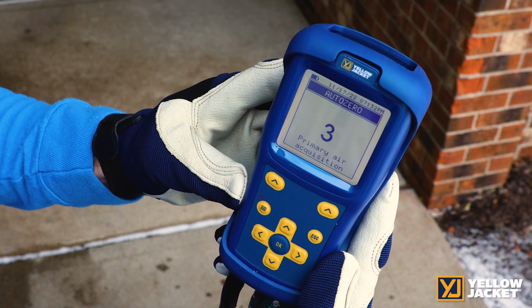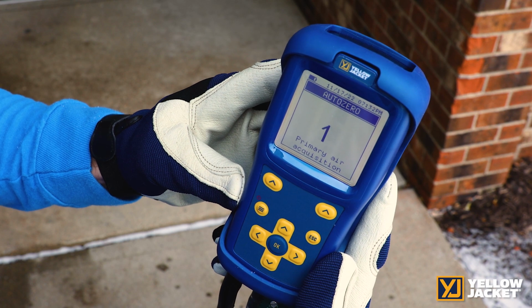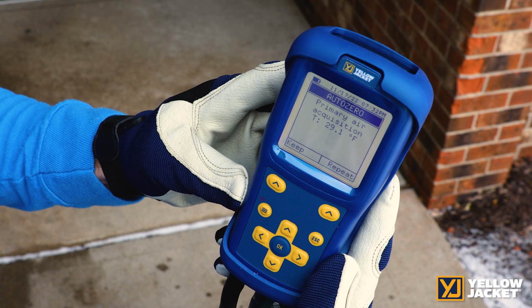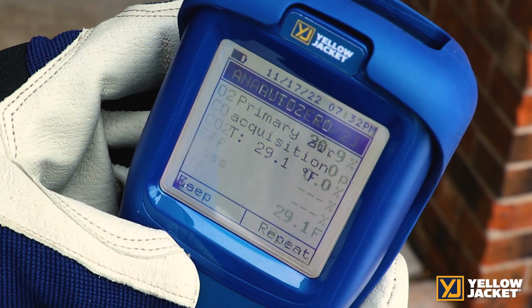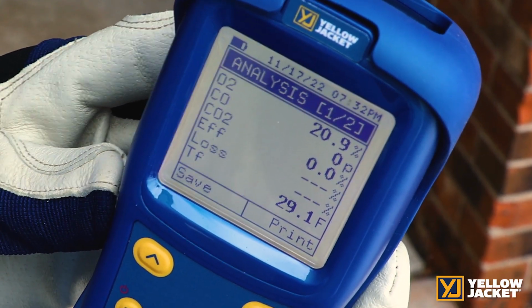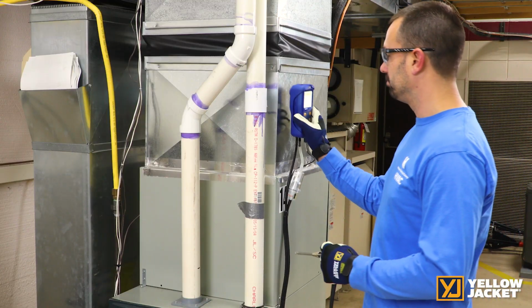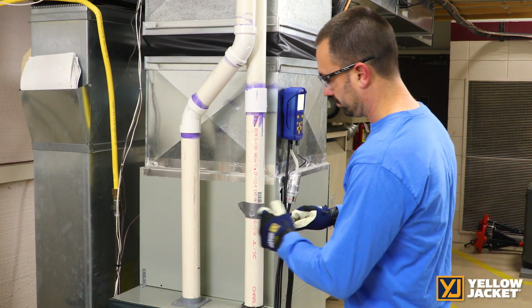This step starts the warm-up cycle and verifies the machine is operational and working properly. You will be asked to keep or repeat to reset your zero. If you started in an area where there may be a CO issue, go to the fresh area and hit repeat. Once you have a good zero, tap keep. After you zero the CA502, you'll need to turn on the flame for the system to begin its warm-up.